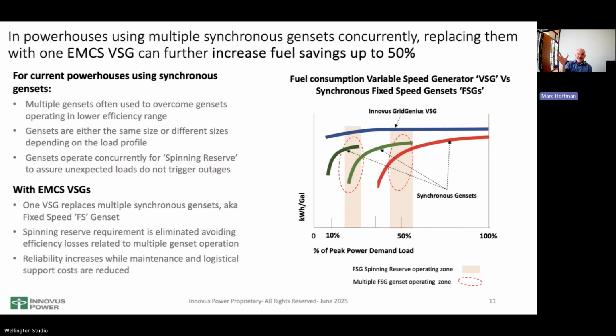Because you can't just turn one on, exceed its capacity, turn it off and turn the next one on, you have an overlap called the spinning reserve area. When a genset gets above a certain load, they spin up the next genset so if the load goes beyond maximum, the next genset picks it up and you don't have an outage. But now you're splitting the load between the two gensets, and you're back into a lower loading situation. So it's the best that can be done.